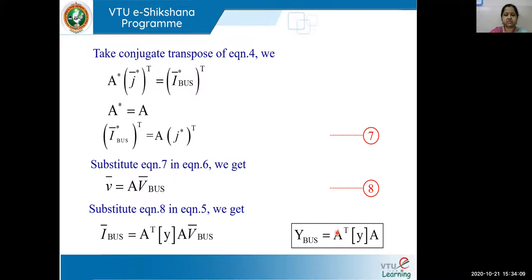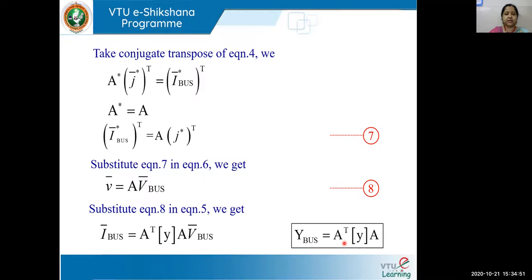Please remember this formula. Finding Y bus by inspection method is simple, but by singular transformation you need to use: Y bus = A^T · YPR · A. The order of A and Y must match. If the orders are not matching, you will definitely go wrong in multiplication. The size of both matrices will not be the same, but the order — meaning the element numbering — must be consistent. Whatever element number you maintain for your incidence matrix, the same element number must be maintained for your Y primitive.